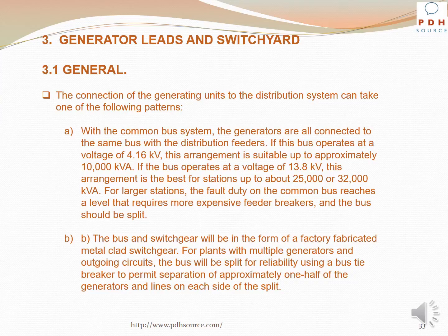The bus and switchgear will be in the form of a factory fabricated metal-clad switchgear. For plants with multiple generators and outgoing circuits, the bus will be split for reliability using a bus tie breaker to permit separation of approximately 1/2 of the generators and lines on each side of the split.